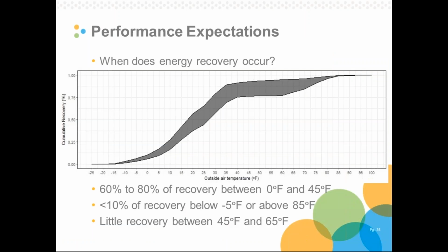All right, I'm going to change tracks here to talk about performance. So we left all these ERVs functioning and with more savings, and now we think they're pretty representative of how ERVs should be performing in Minnesota. So let's maybe use this subset of ERVs to set some performance expectations. This is a plot I'm using for that. Again, it's recovery as a function of outside air temperature. In this case, it's a cumulative recovery for each of these units, and the shaded region represents all 9 units as we left them in the field.